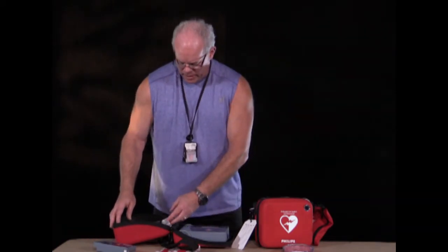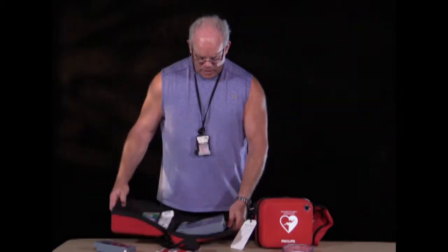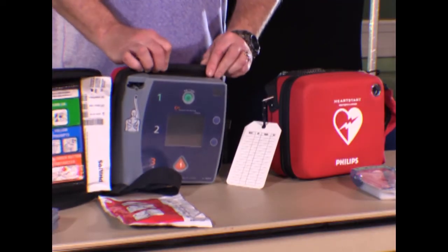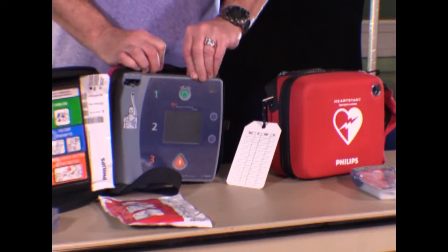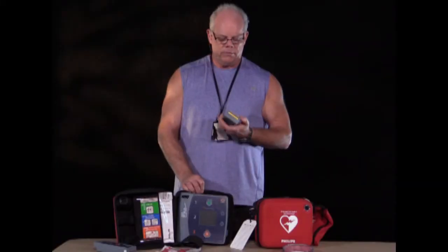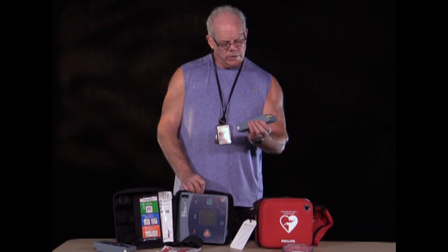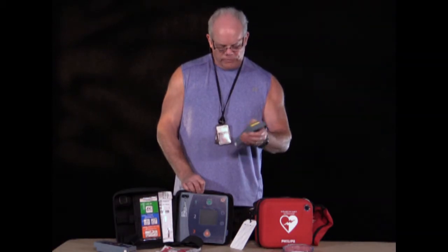You check the pads to make sure that the date is correct. We would check the battery to make sure the date is correct. On this model, if you need to replace the battery, it's on the top, and then you can press the yellow handle on the back and pull it out. To look at the date, this one is good until March of 2017.